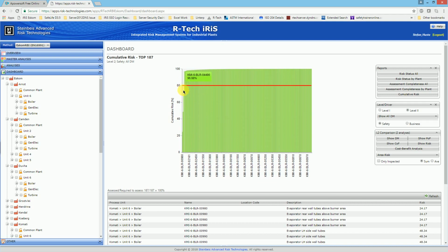And these were some tubes which I'm not 100% certain myself, but that were gauged to be in such a position where they could possibly leak outside the boiler casing and cause fatalities. Hence, they scored extremely highly, and then everything else scored much, much lower compared to that. So again, something that is showing the user what they should maybe pay attention to.